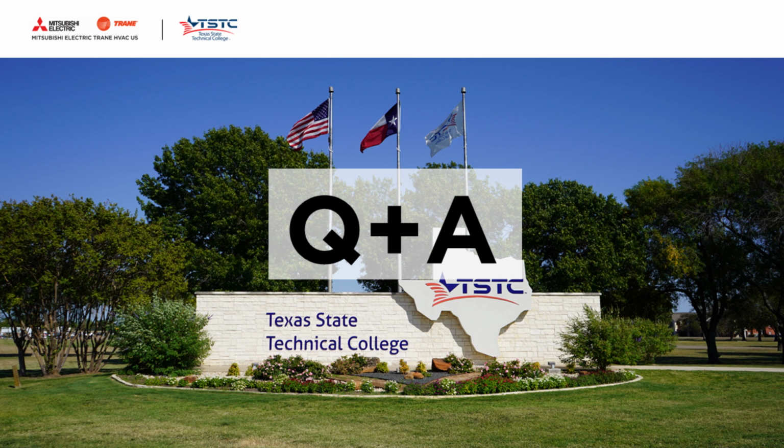Okay. The maintenance is a good point. As you all know, there are a couple of brands out there offering VRF systems, with different branch circuit controller designs. The way Mitsubishi Electric Trane provides the branch circuit controller, when it gets installed, you will most oftentimes want to have access to the bottom of the unit, right? So if you imagine that branch circuit controller up above you, you'd have an access panel in that portion of the ceiling so that if needed, you could get to it.